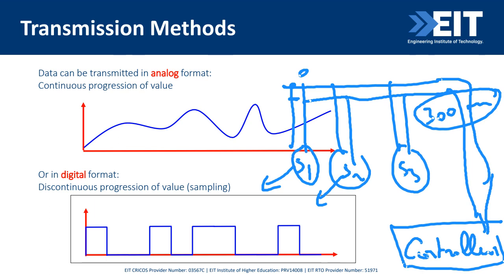Imagine I'm using a pressure sensor. It measures pressure, but it detects an error in its own configuration. It can tell us so. It can send us this information. This could be very useful for safety, for example. I might be able to configure that sensor online. So send the data to the sensor. So not just receive data from the sensor, I can send to the sensor. So I can configure, I can calibrate the sensor on the network while sitting 300 meters away from those sensors.